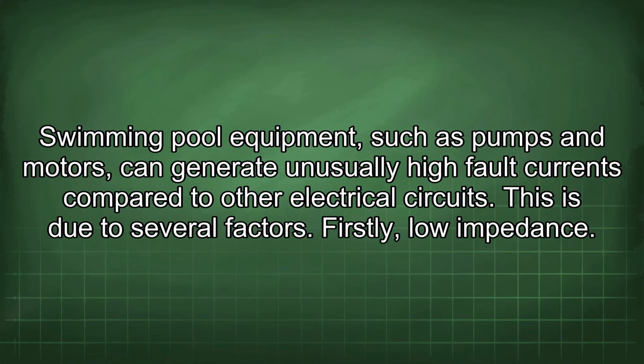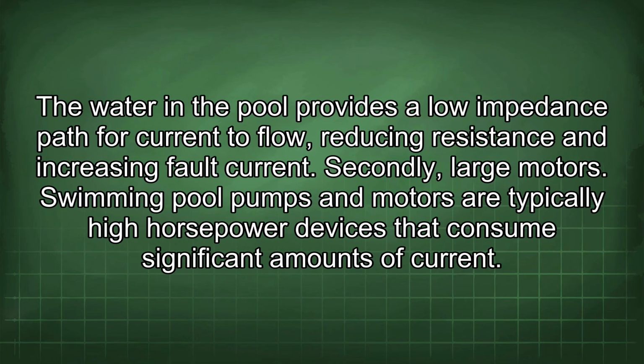Swimming pool equipment, such as pumps and motors, can generate unusually high fault currents compared to other electrical circuits. This is due to several factors. Firstly, low impedance. The water in the pool provides a low impedance path for current to flow, reducing resistance and increasing fault current. Secondly, large motors.